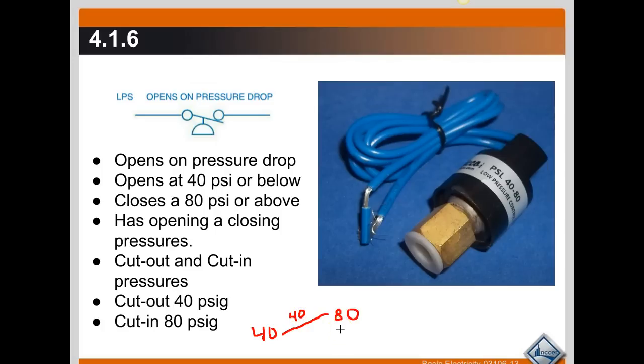Now if it's a safety control like this low pressure control, it should never be in the cut-out condition. And if it is, that indicates you're having a problem with the system.